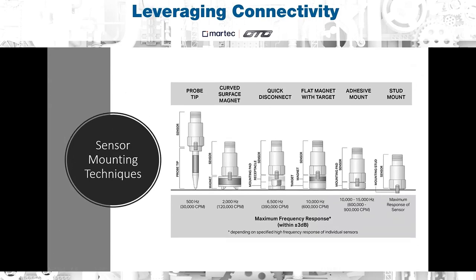So frequency response is very important in terms of the defect that you're looking to monitor. If you have a very small range that you're able to monitor, for example, if you were to use a probe tip, the maximum frequency response you'll be able to monitor is only 500 hertz. So if you're looking to find a type of defect that's present in the bearing, it's very likely that that defect is going to show up at a frequency higher than 500 hertz. So for that reason, utilizing a probe tip would probably not be the best option. I use the example of lubrication, as that is something monitored at 23 kilohertz or more.